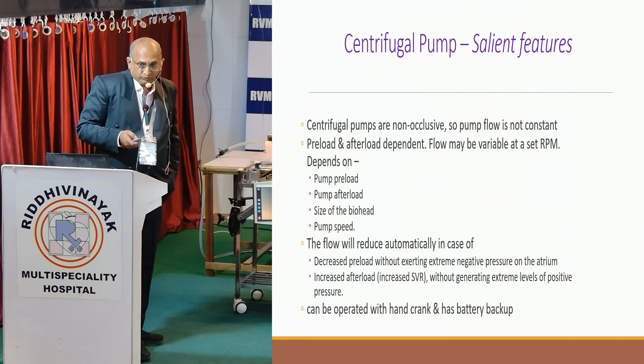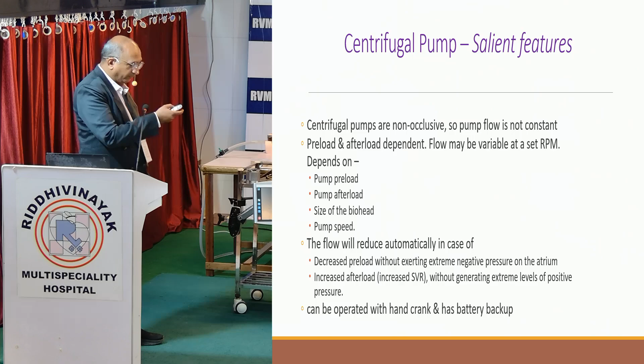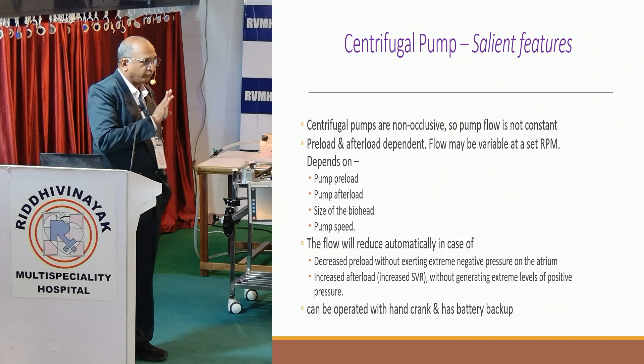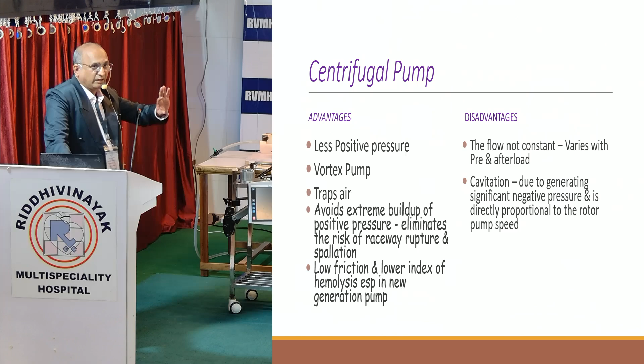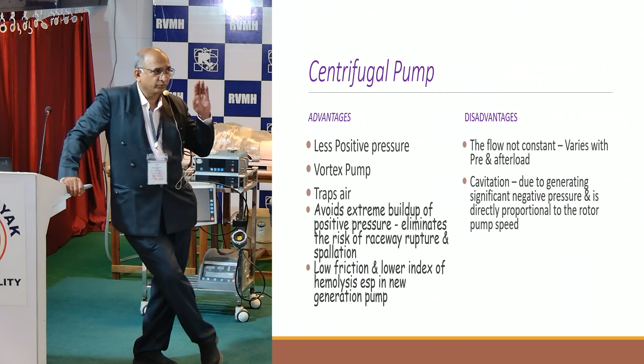So as I told you, the centrifugal pump depends on preload, afterload, size of the pump head, and pump speed. These are the 4 factors on which the flow RPM ratio depends. The advantage is that it creates less positive pressure, so you don't have any chance of tube rupture in case of centrifugal machines. Only if the circuit pressure goes above 400 is there a chance of tube rupture. Otherwise, there is no chance of tube rupture in case of a centrifugal pump.